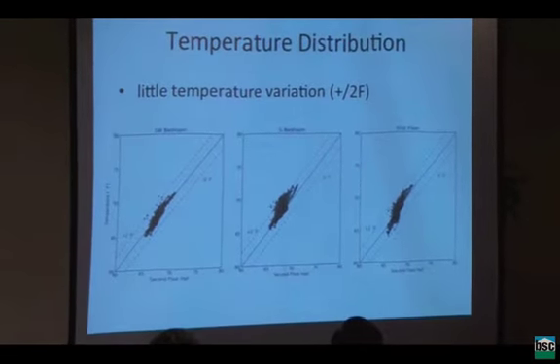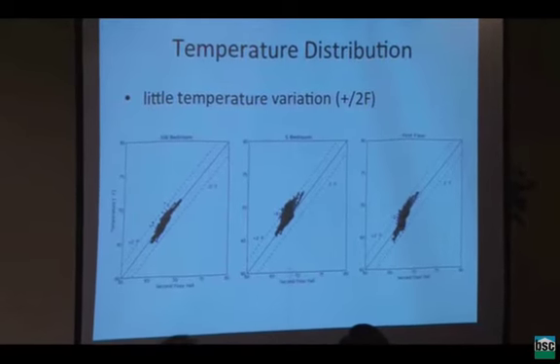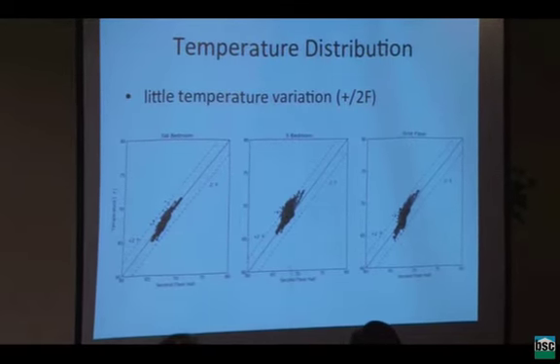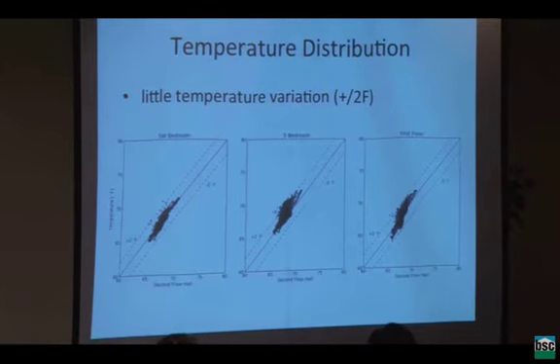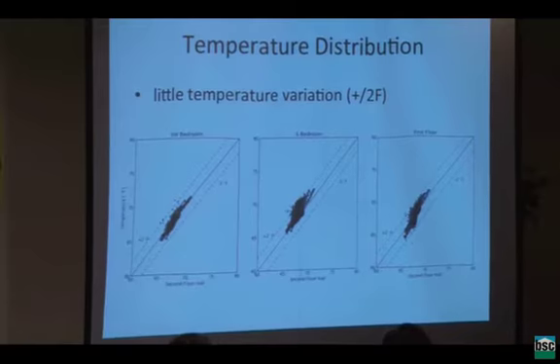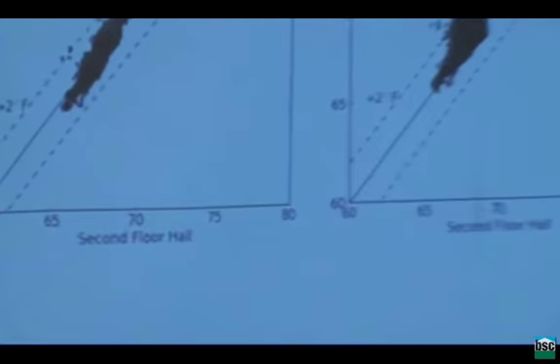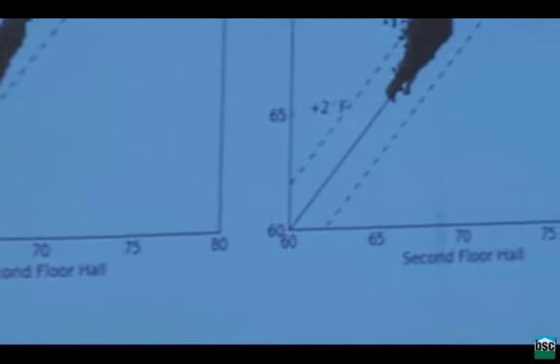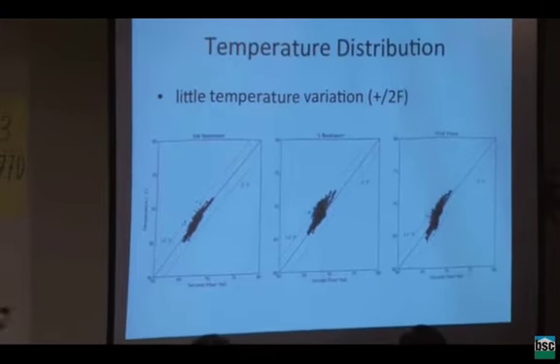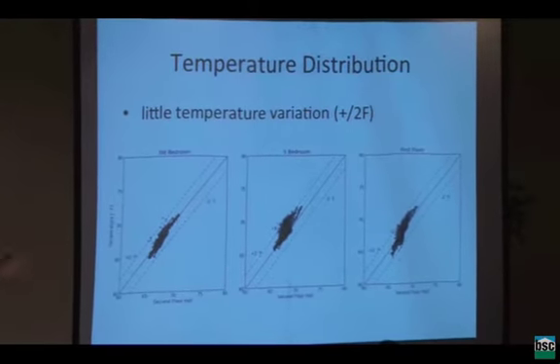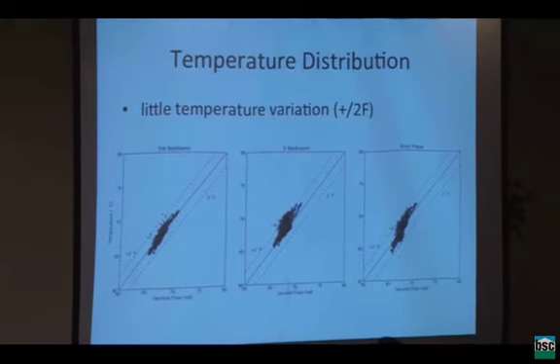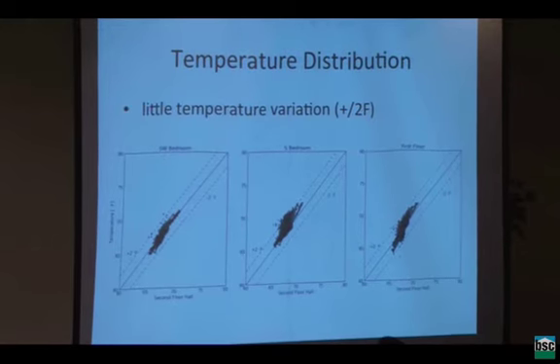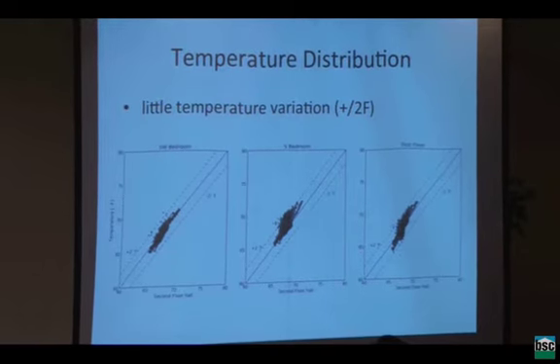The vertical axis is the temperature in the bedroom or 1st floor, and the lower axis is the 2nd floor hallway. So we use the 2nd floor hallway as where the thermostat is. That's the baseline, and then we look at the temperature at the same time in the southwest bedroom, south bedroom, and 1st floor. This is actually wintertime, yes. And so under these conditions, up until about May, they're within plus or minus 2 degrees most of the time. This is really good. These are really good results. No one should ever complain. And frankly, they build a lot of these and no one does complain.